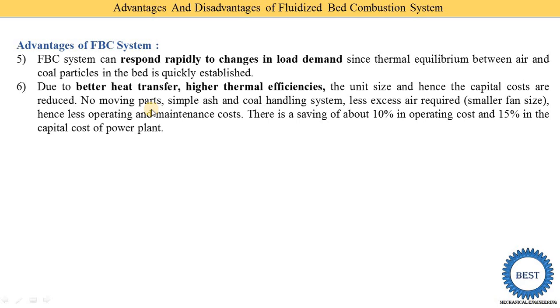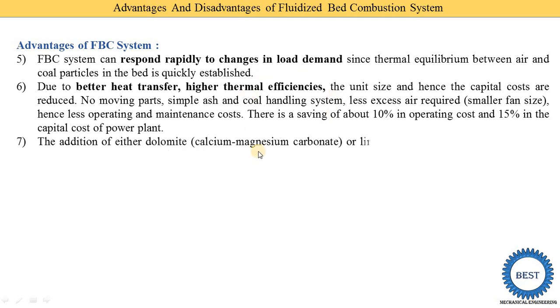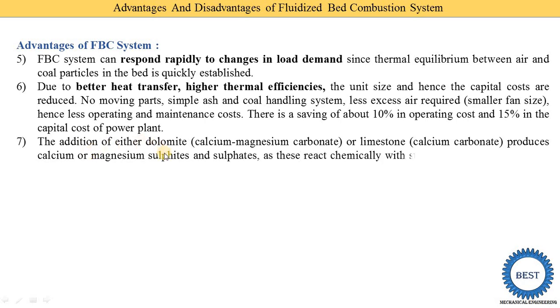Less excess air is required, meaning a smaller fan size is needed, resulting in less operating and maintenance cost. There is a saving of about 10 percent in operating cost and 15 percent in capital cost of the power plant compared to other combustion systems.